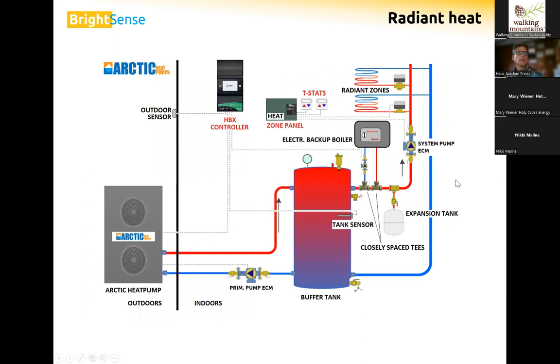Now we're getting to some plumbing. This is what a typical hydronic heat pump system would look like. So very simple, straightforward, your radiant heating system with the zone valves, your thermostats, your zone panel. Here's our heat pump. Heat pump loads the buffer tank with hot water. The buffer tank has two purposes. One is during those 5 minutes when the heat pump is in defrost, we would be feeding off of the buffer tank, so there would be no delay or no interruption to space heating.